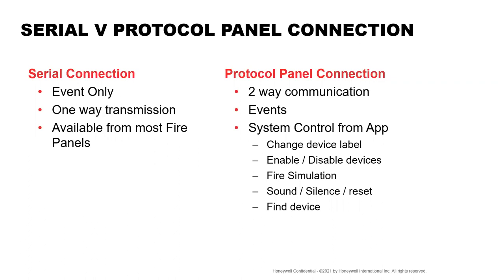Basically, what that means is when you have a detector in a room, when it goes into fire, on the fire panel, it tells you where that device is, and it will give you what we call a label. So it might say downstairs cloakroom, without having to go into the panel and type on a keypad or getting a laptop out and doing all that. You can now do it. You can change those device labels. If the building's moved and changed, you can change that information.